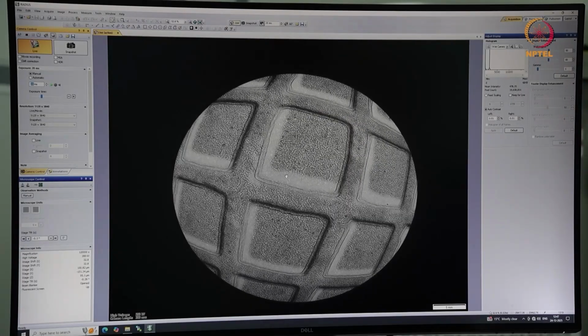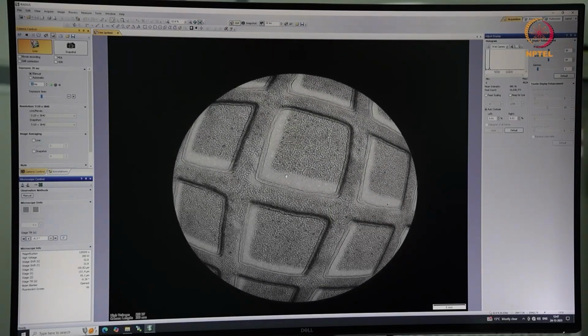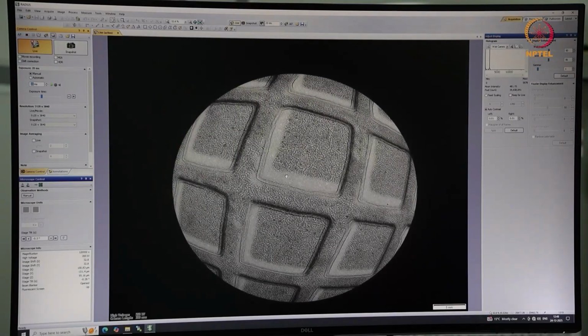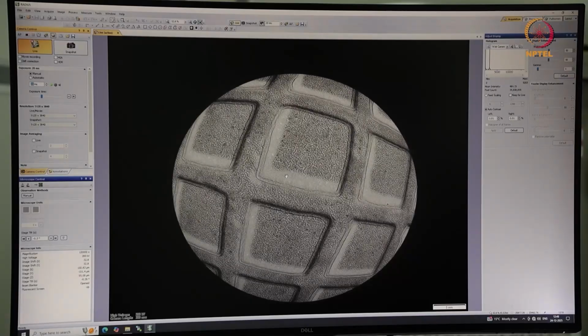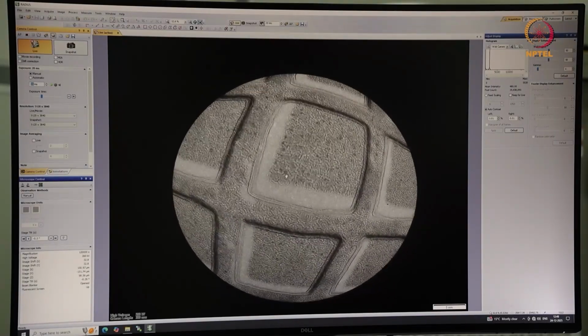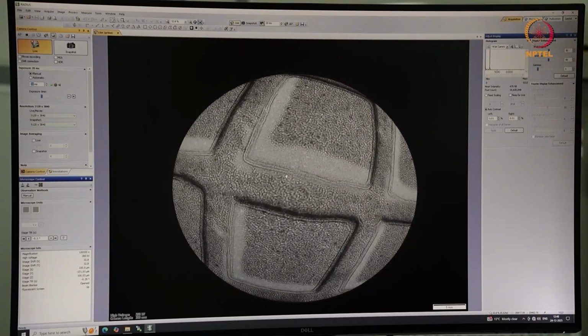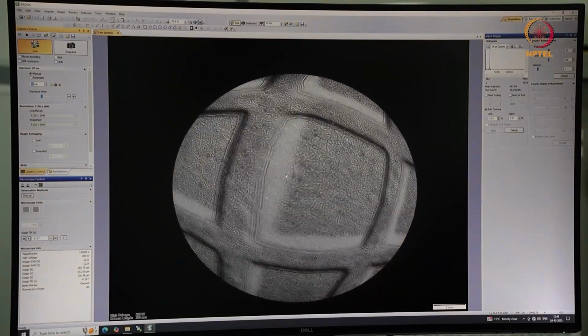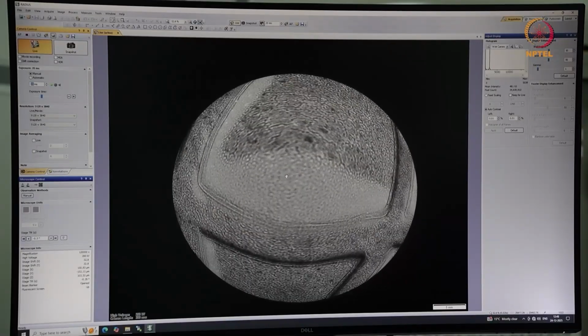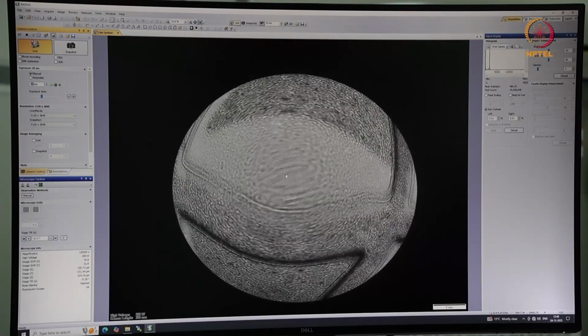And even to correct for the condenser astigmatism, I need to go into an amorphous area and I have to bring the specimen to the correct height. I have done the eucentric adjustment of the sample for the objective lens. So there may be a difference in the height for the STEM mode versus the TEM mode.